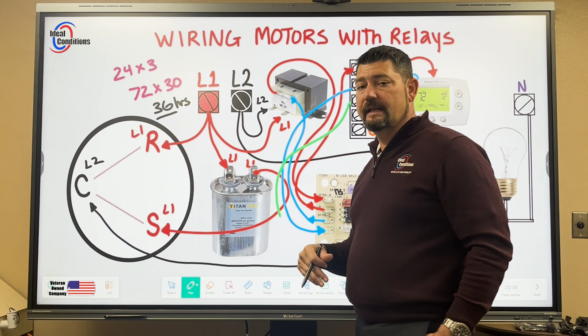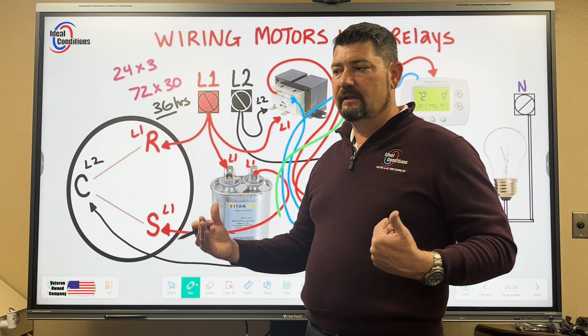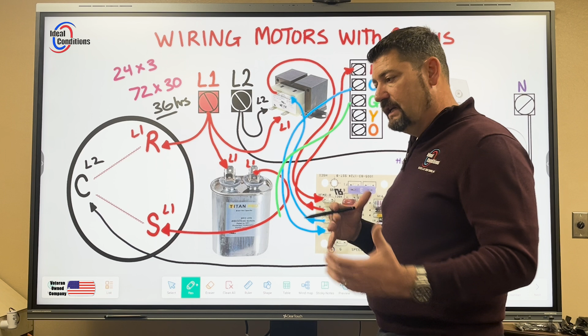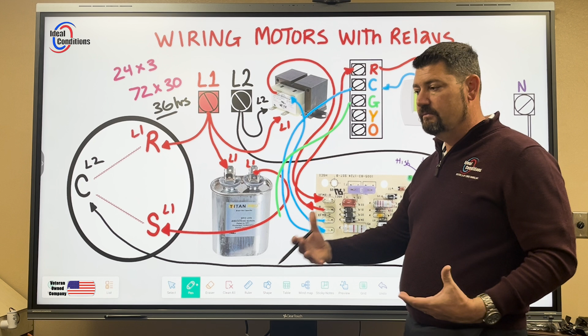And this is when you start getting into bigger things, commercial, industrial. You start getting into dual circuits and compressor banks and lead and lag. And you start getting into condenser fan motors that don't all run at one time, and they don't need to if you can maintain the proper head pressure. All that thinking is all about trying to be conservative and save energy. So you're not just moving more air than you need to, or moving more BTUs at a faster rate. It's not just about the well-being of the structure so we don't short cycle and harm the equipment. It's also taking in the concept of, can we save energy too? Can we get more comfort out of that product?